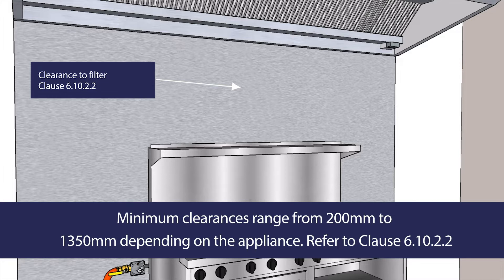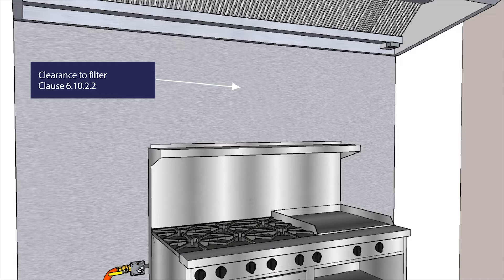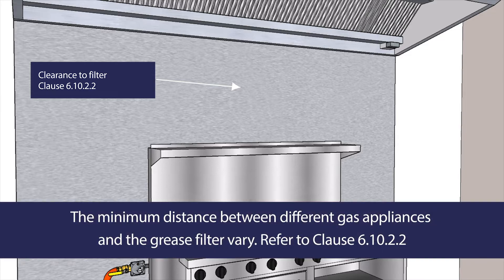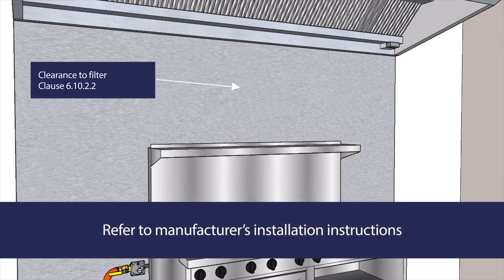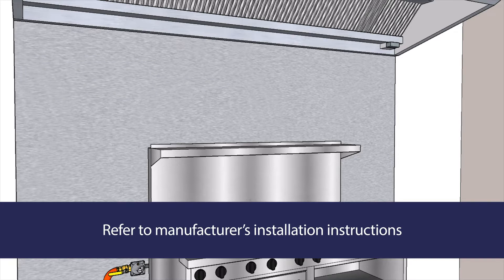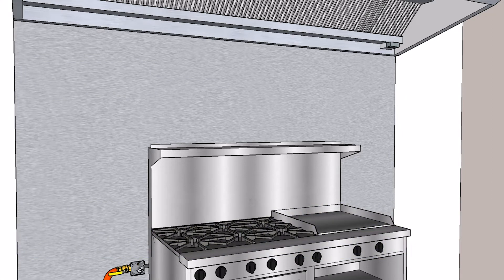This can range from 200mm for a kebab cooker to 1350mm for a range-top Chinese cooking table, griddle, barbecue, char-griller broiler or open-top flare-griller broiler. The minimum distance between different gas appliances and the grease filter varies depending on the type of gas appliance being installed. Refer to Clause 6.10.2.2 if you are unsure of the minimum clearance for each appliance. It is also important to double-check the installation instructions.